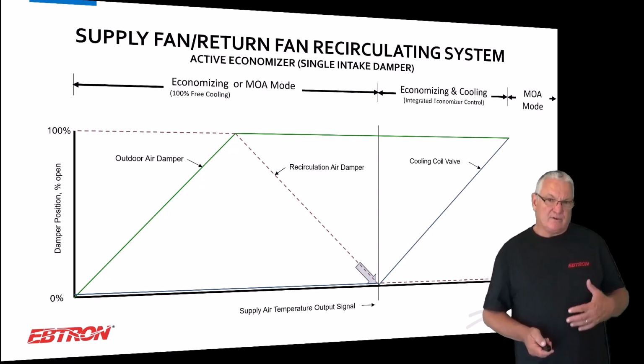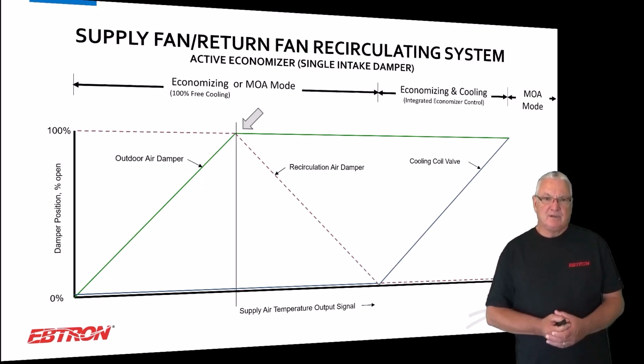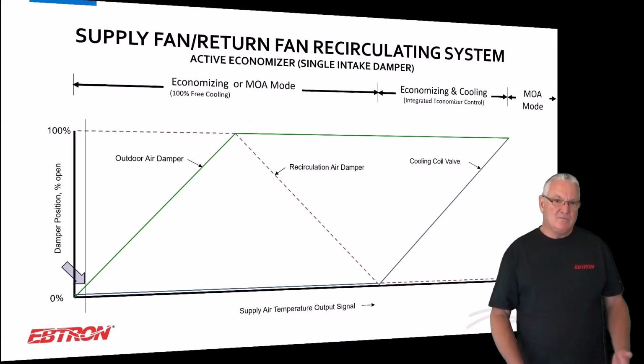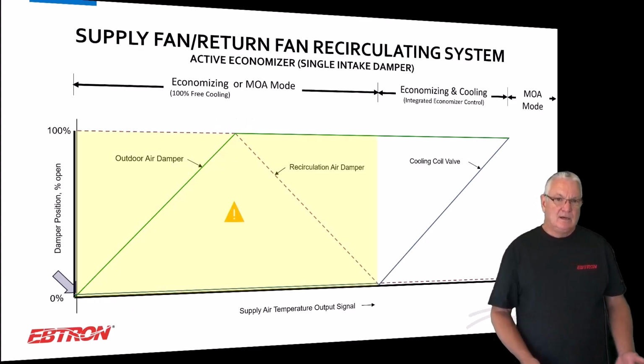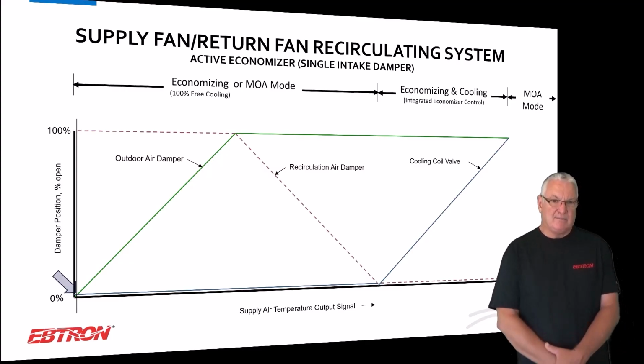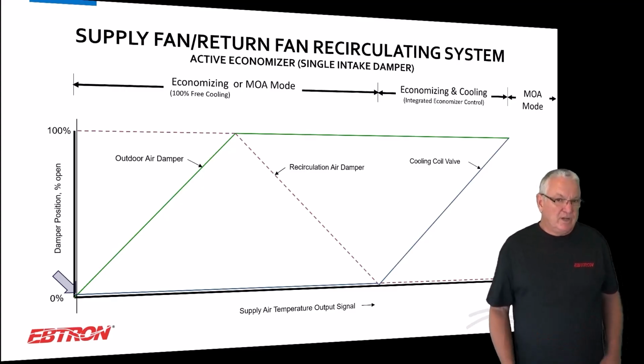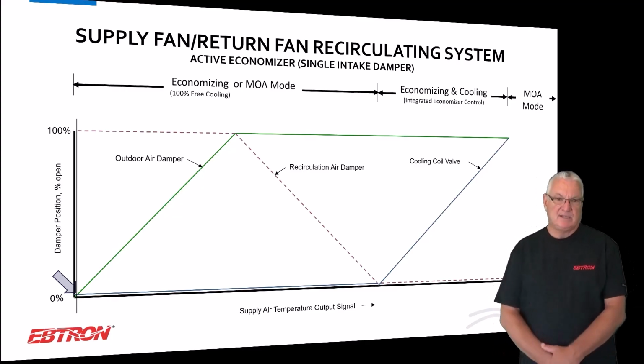And so we're going to first open that recirc air damper, and then if that's fully open, we're going to modulate down. And somewhere down here, I'm sorry, I didn't want to do that yet. Somewhere down here at the bottom, you most likely would have used that. It would probably be relatively cold outside in most applications, but you would say, oh, I'm going to go below minimum outdoor air. I got to go switch back to minimum outside air mode.